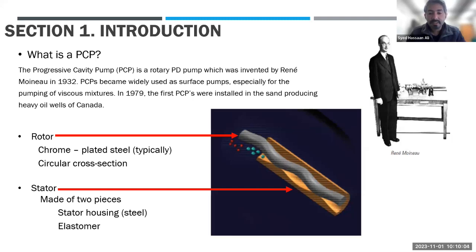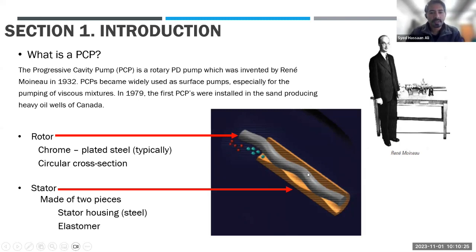It's a very simple system with just one moving component — the rotor. The rotor is a helico-axial rotor deployed in a double helix stator. The rotor is the moving component and the stator is stationary. The rotor is usually made of metal with chrome plating, while the stator — the outside casing — is made of a tube with an elastomer injected into it. That elastomer forms the double helical profile in which the rotor will move.